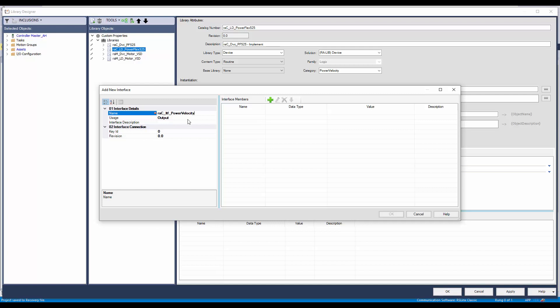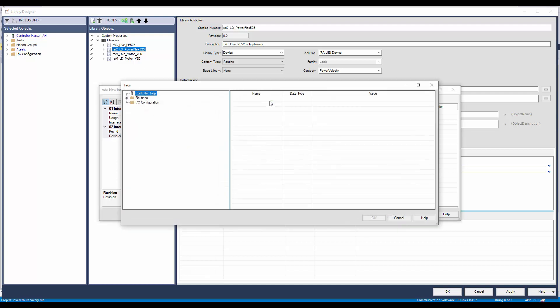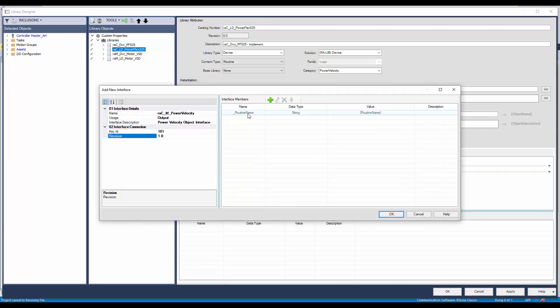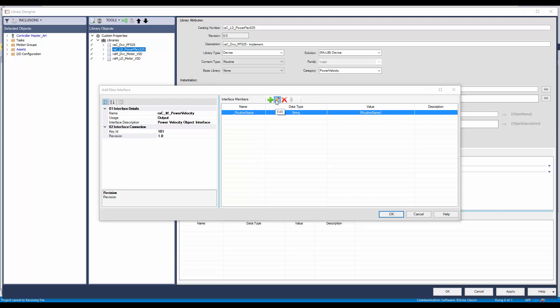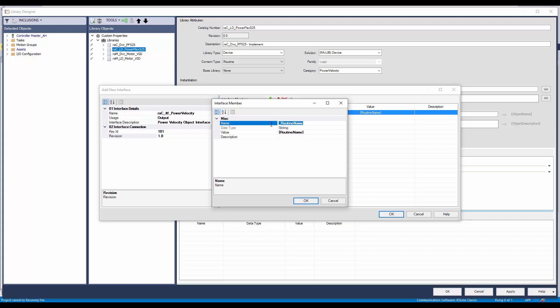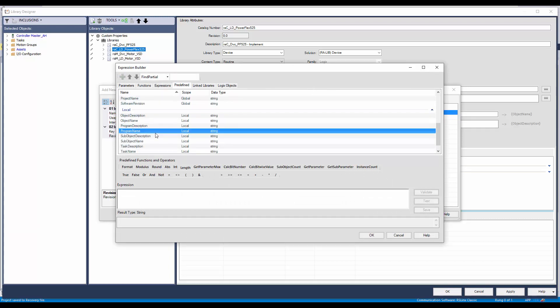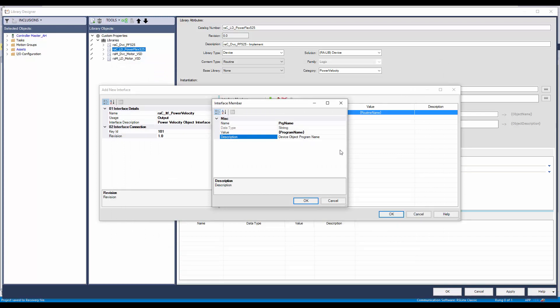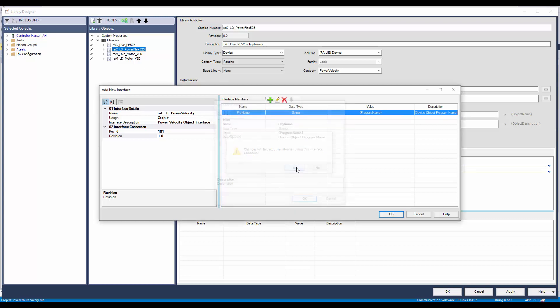Leave the usage as output and enter the description. I will enter a unique key ID as 101 and revision as 1. The next step is to add the members. Click on the add button and select any object like routine name, then click OK. Select the member and click on edit member. I will modify the member name as PRG name and modify the value as program name. Enter the description and click OK. Follow similar steps to add the tag name and module name members.